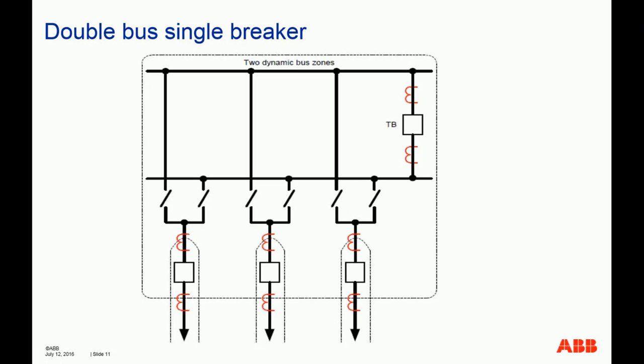However, usually in this type of scheme, you have lots and lots of feeders, 20, 30 feeders connected to the two buses. But each feeder can be connected to either bus A, the main bus A, or bus B. However, the difficulty for protecting this type of bus configuration is that some type of dynamic zone switching must be in place. Because the feeder, the CTs here, this bus CT can belong to either bus 1 or bus 2. So you need to be able to have a means to switch them.